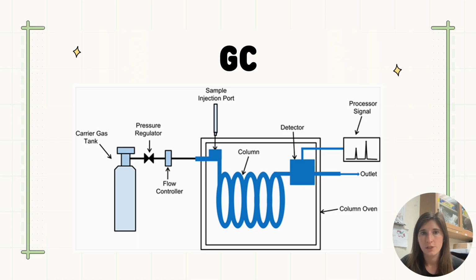For complex mixtures with components of varying retention characteristics, it's often impractical to use a single column temperature, also called an isothermal run. So instead, we're going to systematically increase the column temperature throughout the analysis to dramatically reduce the amount of time it takes for higher boiling point components to elute. And this is also going to improve the sensitivity of the assay, as the peaks are going to be sharper.